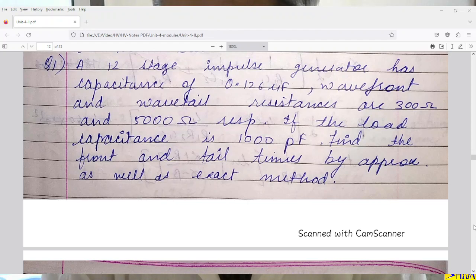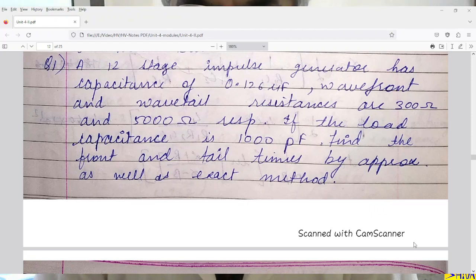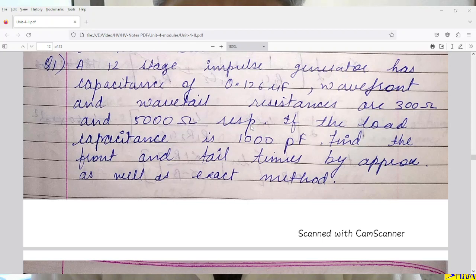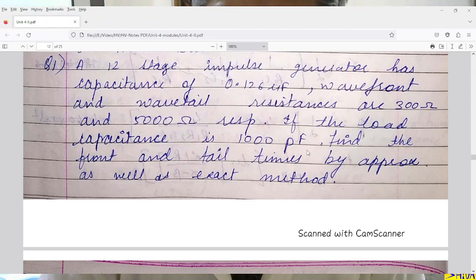In this video lecture, I will take a few numericals on multistage impulse generator. First numerical: A 12-stage impulse generator has capacitance of 0.126 microfarad. Wavefront and wave tail resistances are 300 ohms and 5000 ohms respectively — wavefront resistance means R1 and wave tail resistance means R2. If the load capacitance C2 is 1000 picofarad, find the front and tail times by approximate as well as exact method.